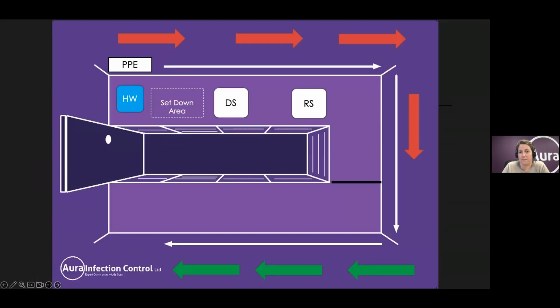So let's pop our sinks in for our manual cleaning. So you would have, at this point, three sinks: your hand wash sink, your dirty and your rinse sink. Bowls are allowed, but they have to be designated for use. And your equipment would be close by: your thermometer, your nylon brushes, your autoclavable gloves, your logs or logbooks for manual cleaning. You might have timers as well if you have a specific contact time that you need to meet. And this process should be observed. So you should be able to watch this process consistently happen the same way, no matter what time of day, what user is doing it. And if that's not the case, you should be able to take some learning from that.